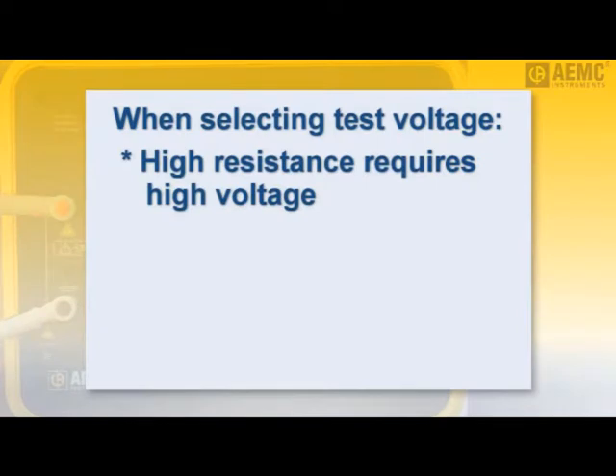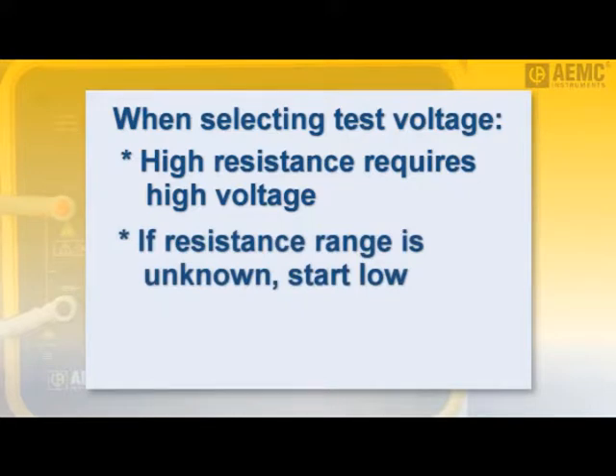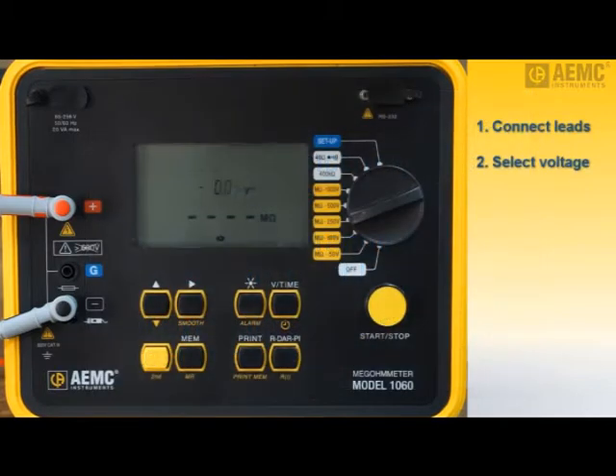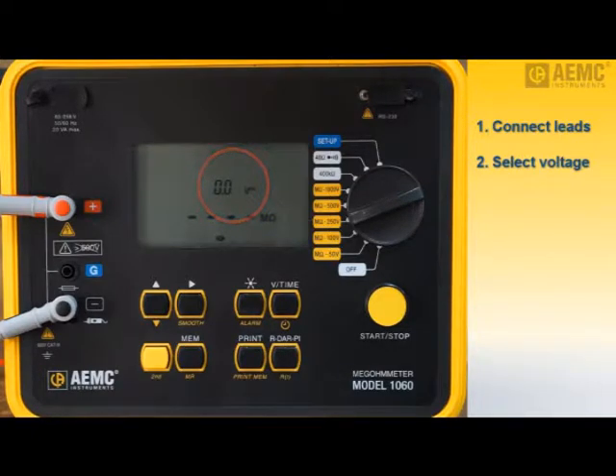In general, the higher the resistance to be measured, the higher the test voltage. In cases where the resistance is unknown, it's good practice to start with the lowest voltage and gradually increase until the measurement results are consistent. As another rule of thumb, we recommend testing at twice the system voltage, as long as the system voltage does not exceed 1000 volts. In our example, we will start with the 250-volt setting. After a few moments, a voltage reading appears on the screen — this is the external voltage present in the test specimen. As a safety feature, if during testing external voltage exceeds 25 volts, a warning symbol appears and the instrument immediately stops the test.